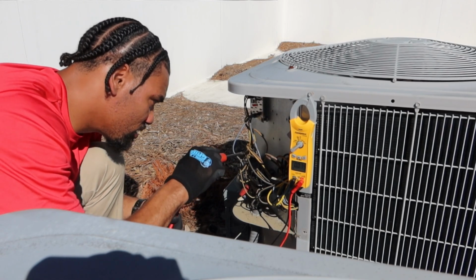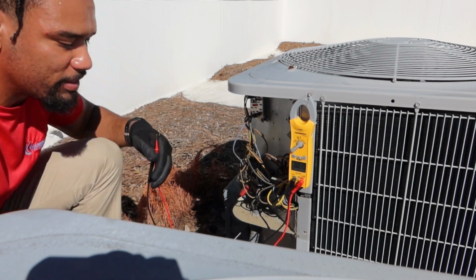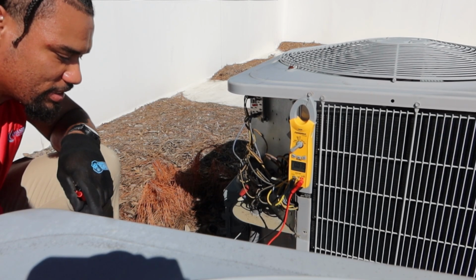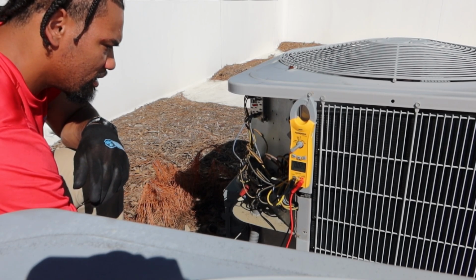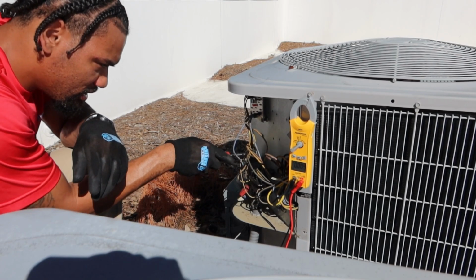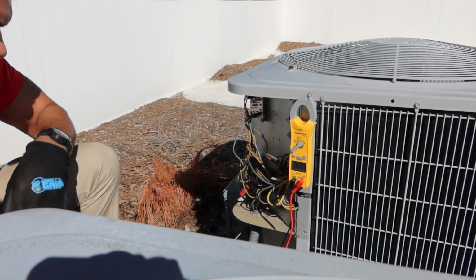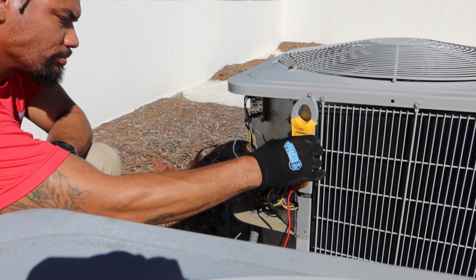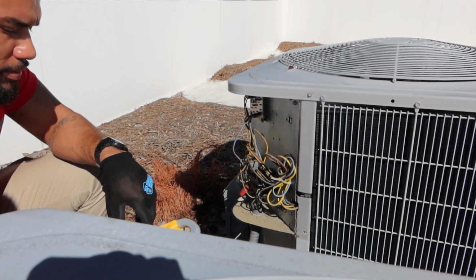All right. So what you doing now? Discharging. Good job. Discharging the capacitor. You confident that it's good in discharge? You put your terminal across both leads? On both, yep. So now you're confident. So now you need to find a rating of that capacitor. If you want to go with your meter first, you're going to put it on capacitor? Yeah.